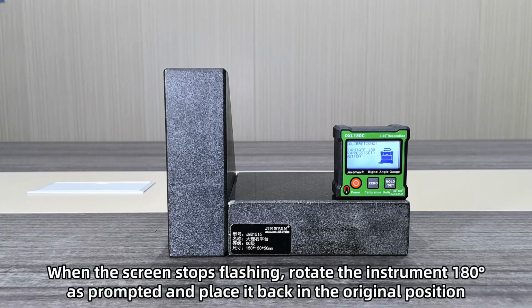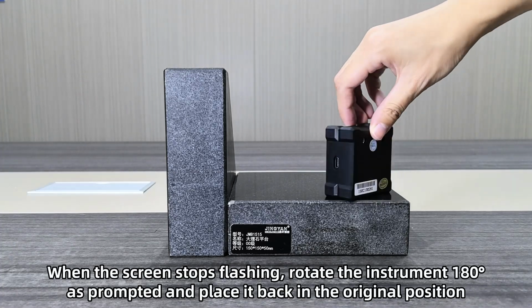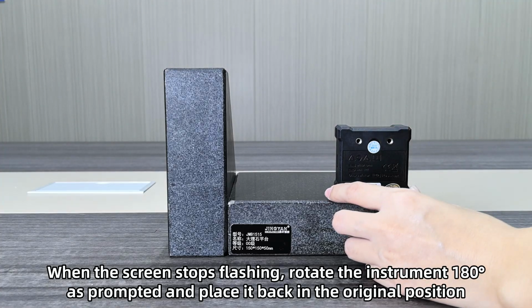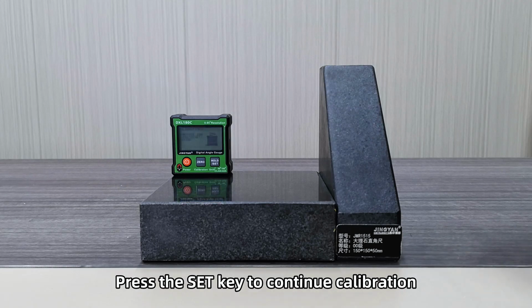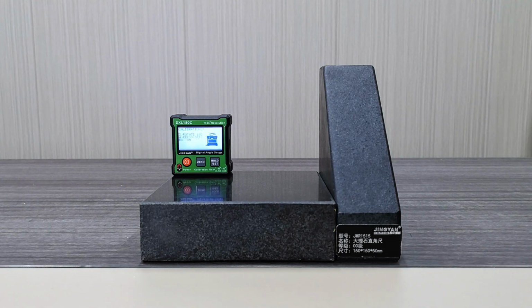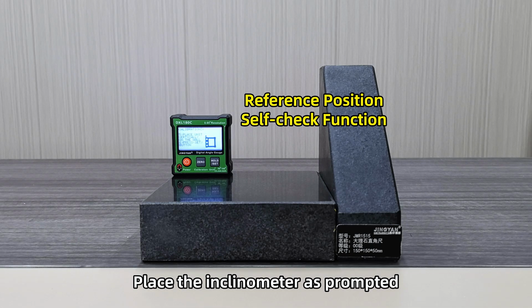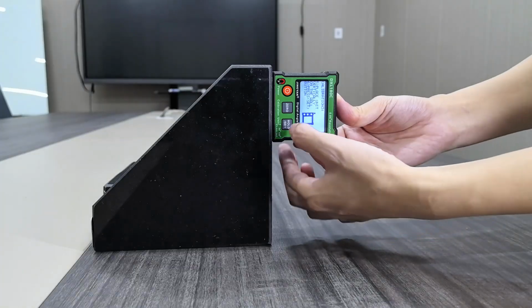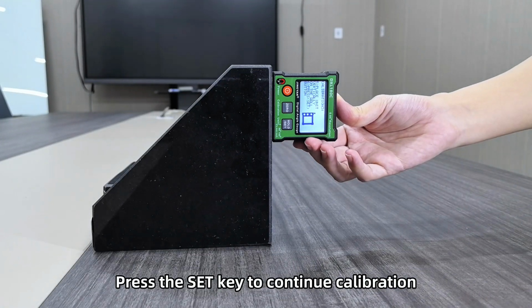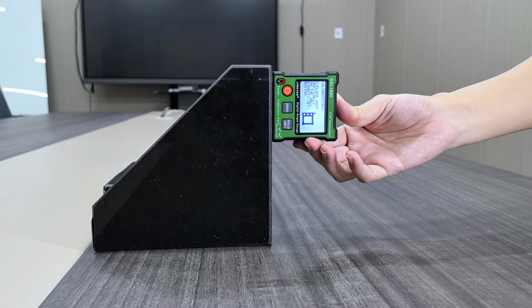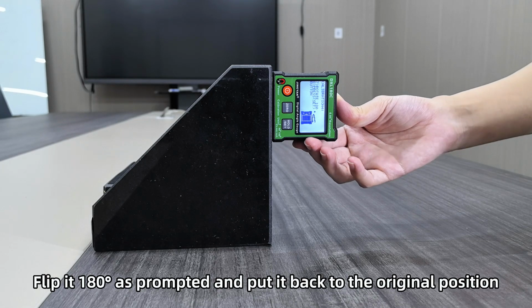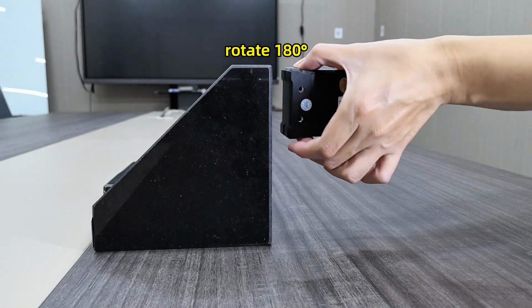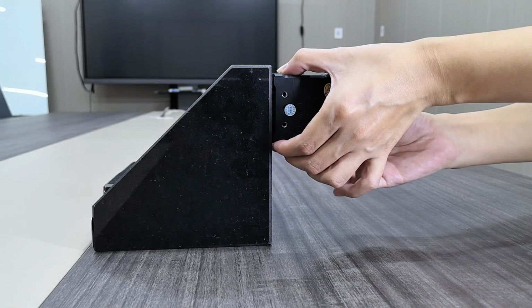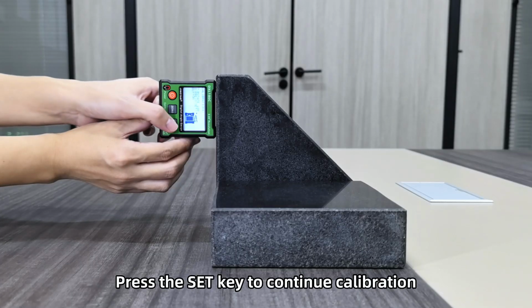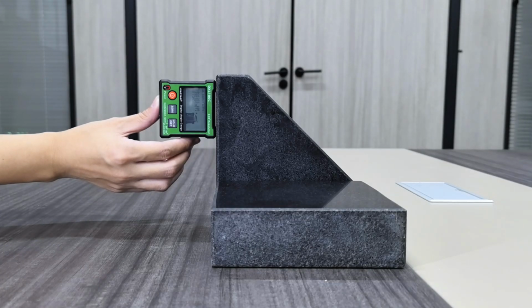When the screen stops flashing, rotate the instrument 180 degrees as prompted and place it back in the original position. Press the SET key to continue calibration. Place the inclinometer as prompted. Press the SET key to continue calibration. Flip it 180 degrees as prompted and put it back to the original position. Press the SET key to continue calibration.